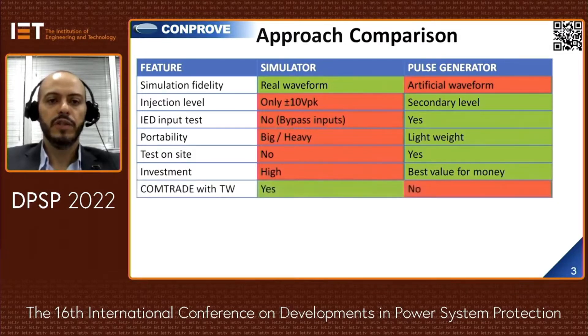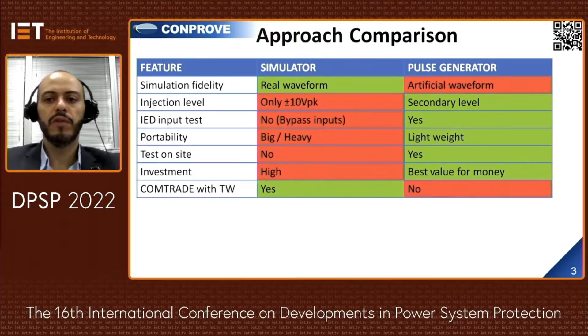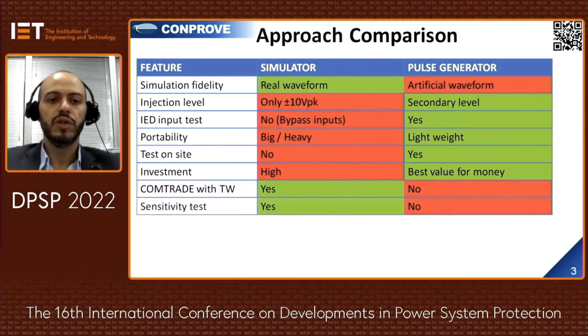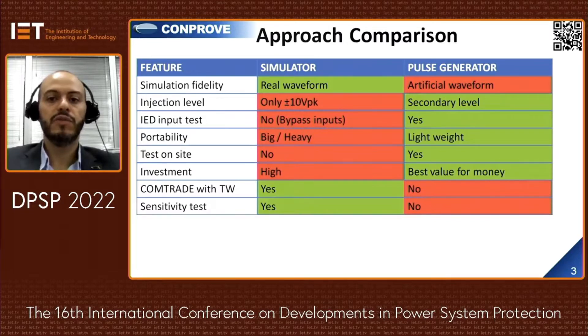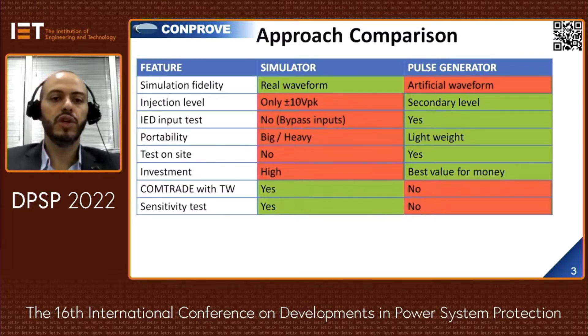COMTRADE simulator can export COMTRADE files with TW content, while artificial pulse methodologies do not have traveling wave data in the COMTRADE files. To perform a sensitivity test, the magnitude of the traveling wave can be changed with resistance — the simulator can do this. Otherwise, pulse generation does not allow changing the amplitude of fault parameters.